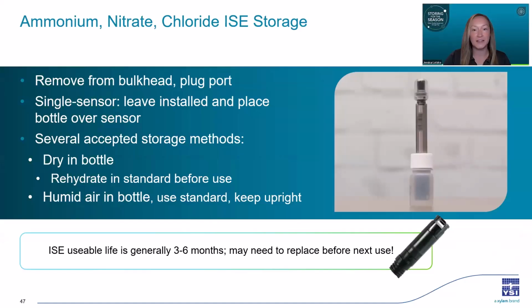We want to protect the sensor membrane during storage, and one way to do this is by using the storage bottle that it came with. Generally, you want to remove the sensor to store it, but you can leave it installed if it's a single sensor instrument and just put the bottle over the tip. There are going to be several acceptable storage methods, so just use the one that's going to work best for you or that is potentially in your SOPs already.